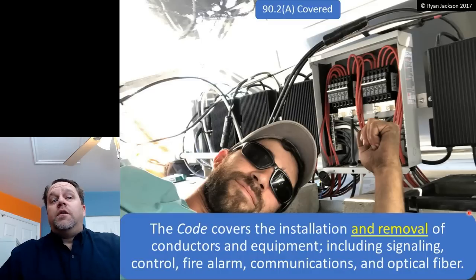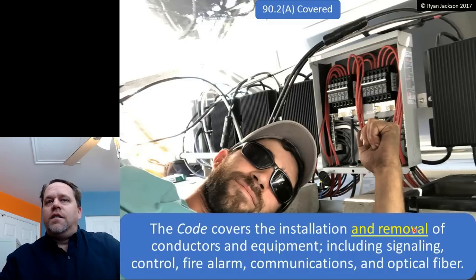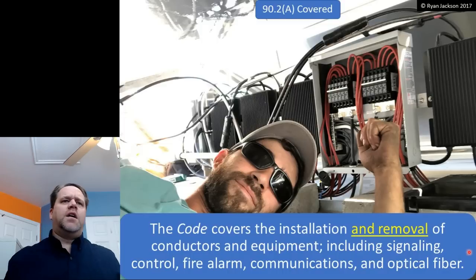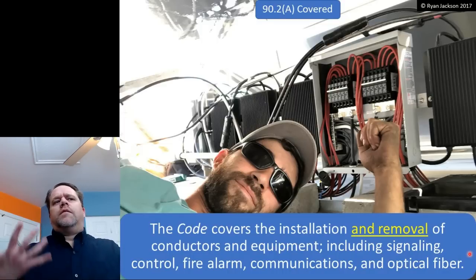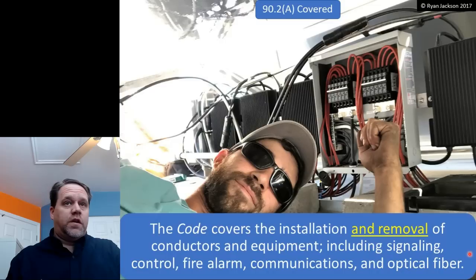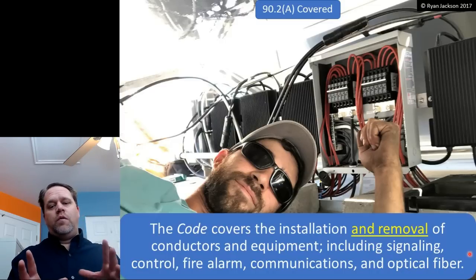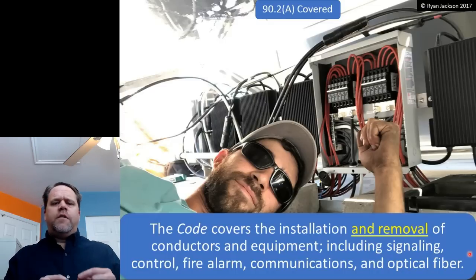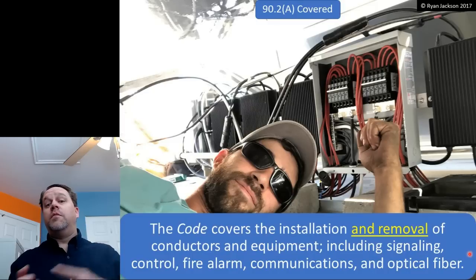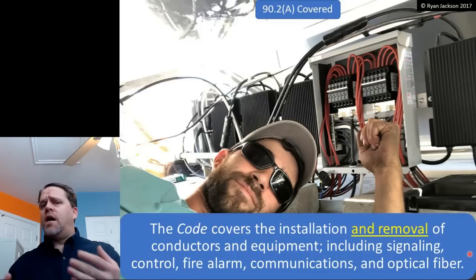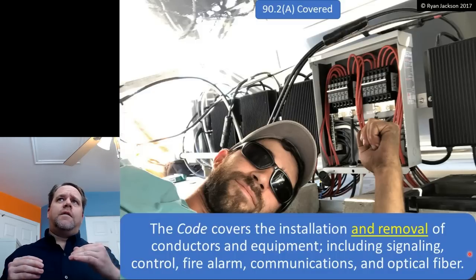control, fire alarm, communications, and optical fiber. Let me get the removal part out of the picture, since that's underlined and in yellow and it's kind of jumping off the page. The code really doesn't cover the removal of conductors and equipment, other than in a few very specific instances.